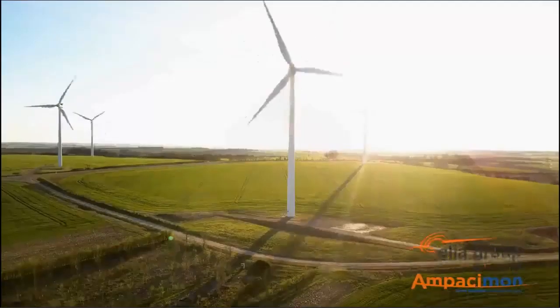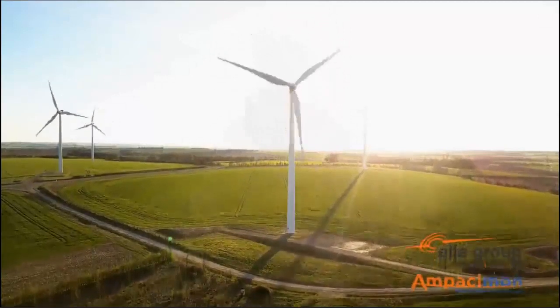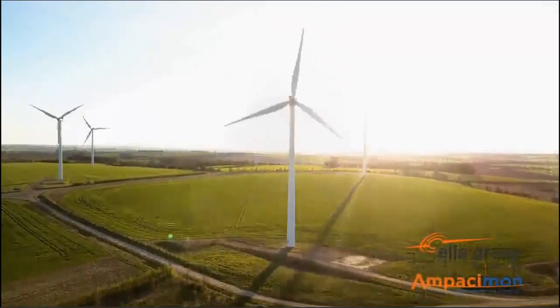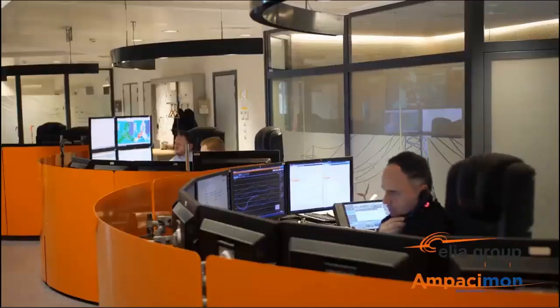There are two big use cases for ELIA using Ampacimon. First one is in real time. Near the coast, we have a lot of wind farms connected, and without Ampacimon before, if there is congestion, the only solution is to reduce or to curtail wind. In this case, once you install Ampacimon, there is less redispatching you have to perform. And it's very interesting to see that there's a correlation between Ampacimon and wind in feed. So the days when there's a lot of wind and higher congestion are also the days where there is more ampacity given thanks to Ampacimon.